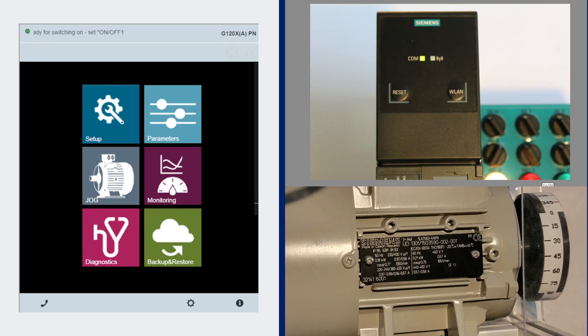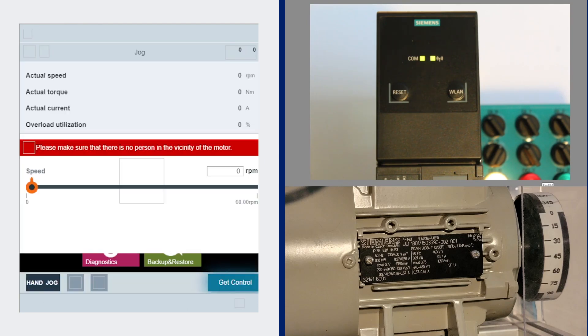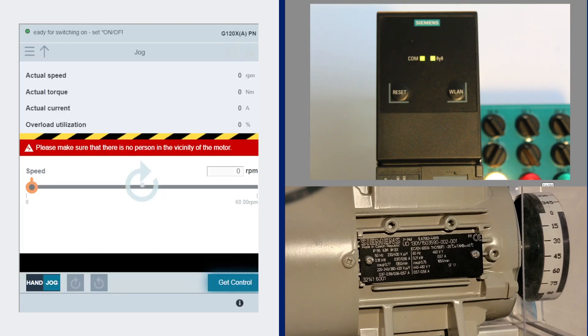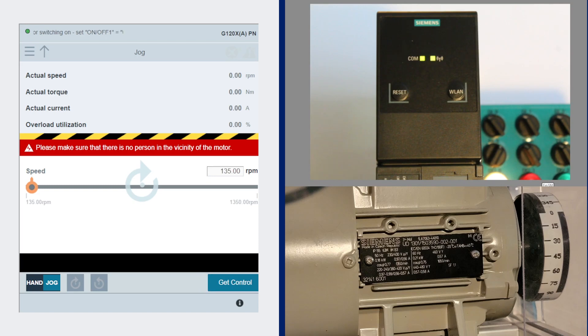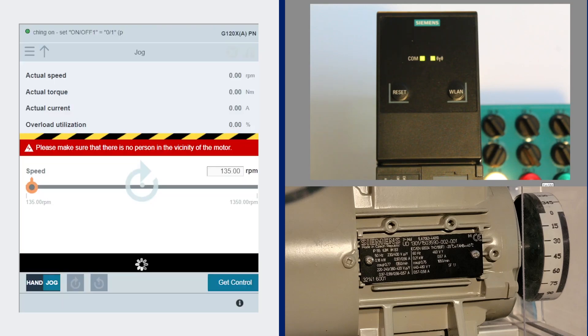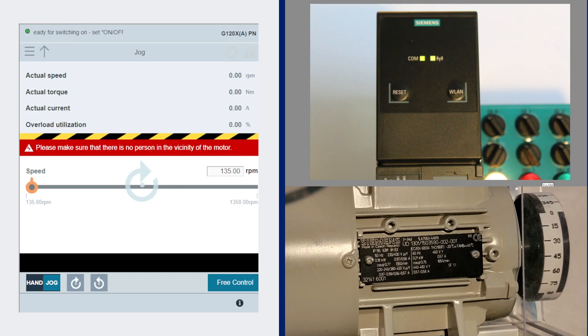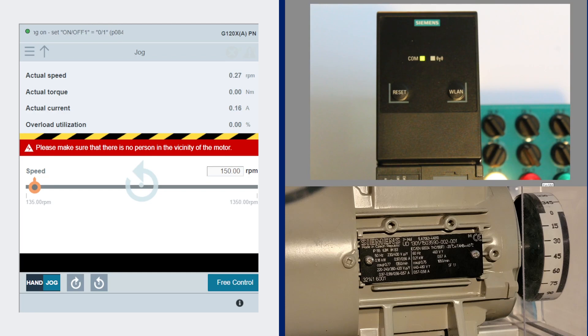There's a jog screen where you can get control of the motor and run it for troubleshooting purposes either in a jog mode where it'll jog at the minimum run frequency.